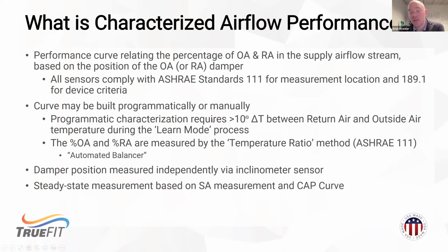for any given position of that mixed air damper assembly. This is very similar to a pump curve for fluid, where if we know the speed of the pump and we know the pressure, I can tell you the flow through. Here, the way it works for TrueFit is, if I have my curve and I know the position of the mixed air damper assembly, that will tell me the percentages of OA and RA that are present in the supply airstream. The supply airstream gives us our total, and then we can break out the percentage based on that performance curve. This curve is a multi-point curve, and it can be programmatically built by the controller.